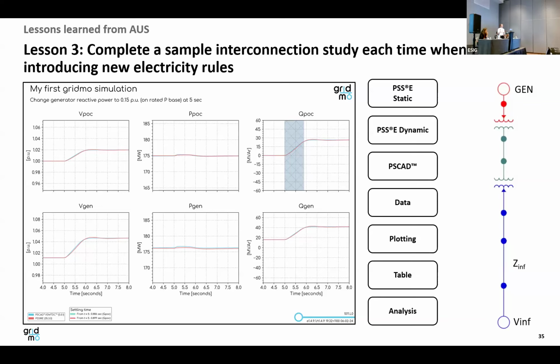What we've seen is it's very easy to write a rule with this, but what I highly recommend, and I'm talking to people in Australia about this, is run a phantom project. Run a 100 megawatt solar farm using WECC generic models on a 50 bus network. Just run it through the lens of whatever rule you're doing, and you'll discover a lot of the nuance that you need to define. Going back to the lesson 1 example of defining your terms, you would have had a team looking at that and saying, well, I thought maximum continuous current was this. Well, I thought it was this. If you're going to get the entire industry to spend trillions of dollars and put all this investment in, just run a blank project and learn a lot from that.